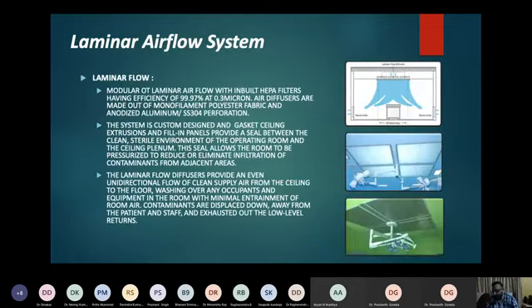Next is the most crucial portion of the modular OT, called the laminar airflow system, also known as the air ventilation system. The air supply to an operating room should serve four main functions: first, to control the temperature and humidity of the space; second, to assist in removing and diluting waste anesthetic gas leaking from anesthetic workstations.